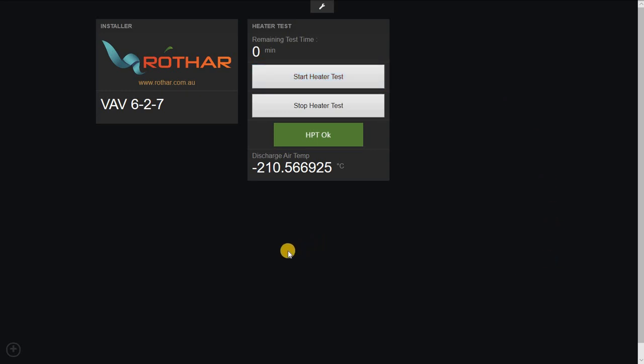Again, this is what the commissioning guys will do. It sets the test for 60 minutes. So they set the test. If the test fails, they can reset the HPT, reset the test, do it again. It gives them a full 60 minutes of testing of the heater to make it so that the VAV controller isn't overriding any control of the heater.